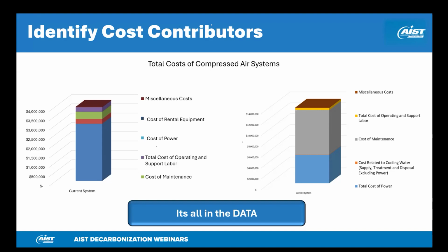Is there enough excess heat to apply an organic Rankine cycle system to produce electricity? I would say we would calculate each compressor based on the horsepower. If you take the horsepower of the machine times 2545, that gets you your BTU per hour, and then you can look at the heat rejection rate of that compressor. There's ambient air, there's cooling air, and there's cooling water for each application. So based on the horsepower, you can calculate the BTU per hour that needs to be applied to other processes. And if that meets the requirement for the cycle, then you can look at an application to use it.